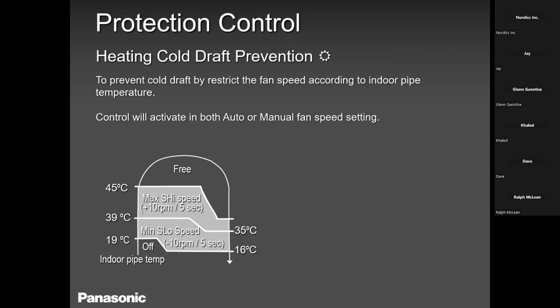Cold draft prevention, guys, is when you turn on the unit for the first time in heat mode, the fan will not come on. And after the coil is nice and toasty, like 46 degrees and above, then the fan will be running at full blast. At that point, you can lower the fan speed or increase the fan speed or whatever you want to do. But at 16 degrees Celsius and below, the fan is off. As soon as the coil temperature gets above 16 degrees, the fan will start very low, and as soon as it goes above 35 degrees, it's going to go to max.